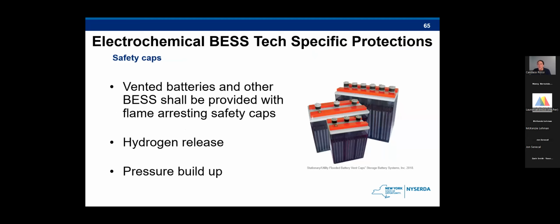So next requirement is the safety caps. So basically vented batteries and other energy storage shall be provided with flame arresting safety caps. So hydrogen is a byproduct of lead acid battery charging and discharging process. So rooms or containers that have these systems should have a ventilation fan inside that will turn on when flammable gases in each room reaches 25% of the lower flammability limit. In regards to valve regulated lead acid batteries, the gas is captured and then released when the pressure on the safety caps reaches a point that is considered overpressurized, and the caps will open and release the gas buildup. So once again, this is not a requirement for lithium ion.